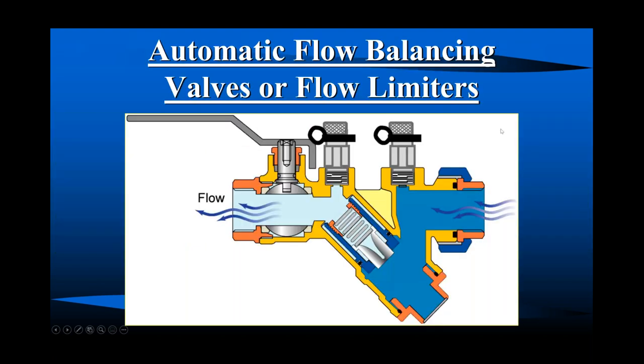This is the cross section of an automatic flow balancing valve. It has a variable orifice. Here's our path of water through this device. This is the device we'll talk about next. We call it a couple of different names: cartridge, piston, can. It is a variable orifice. This is a cross-section of a spring, and that pushes this pie-shaped orifice out into the water stream, depending on certain conditions, and that is a variable orifice.